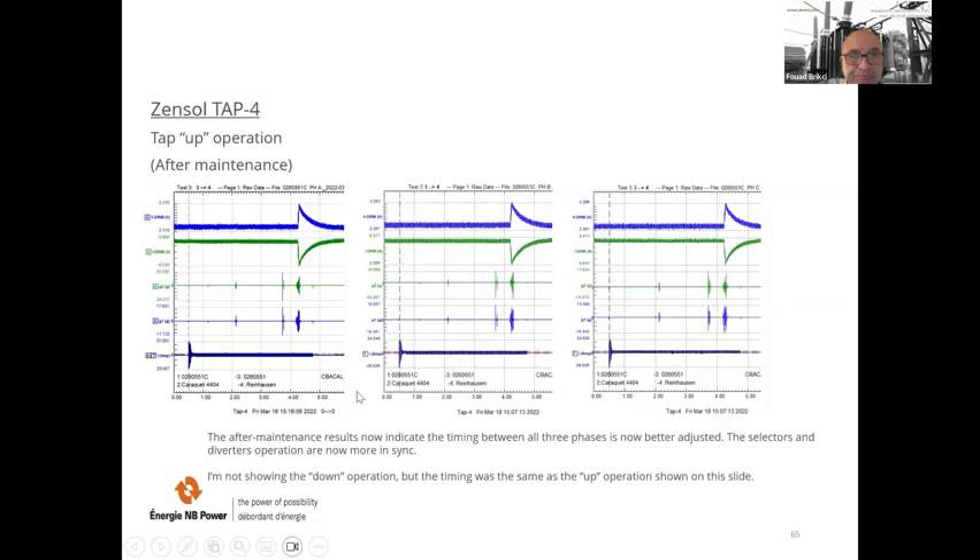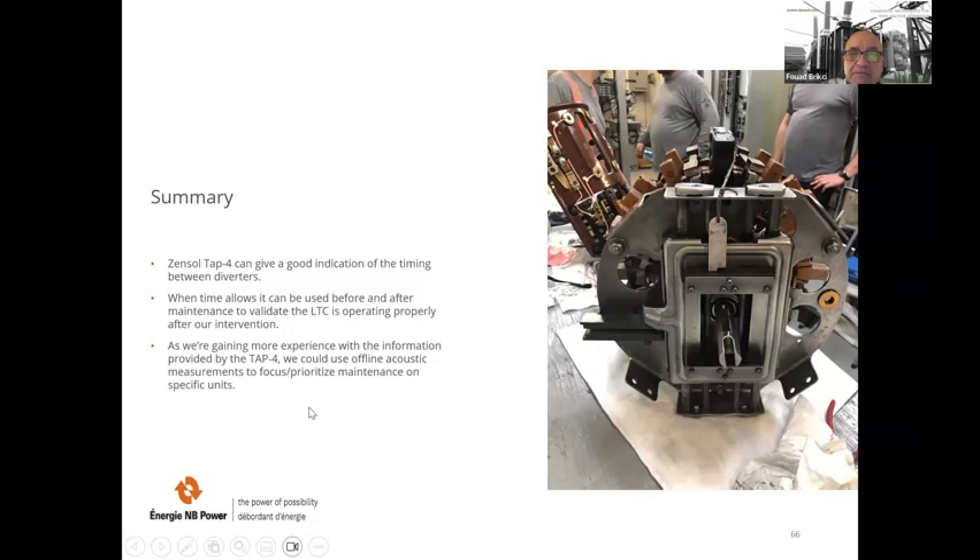In summary, the Zensol TAP-4 can give a good indication of the timing between diverters. When time allows, it can be used before and after maintenance to validate the LTC is operating properly after intervention. As more experience is gained with the TAP-4, offline acoustic measurements could be used to focus and prioritize maintenance on specific units — exactly the kind of benefits described at the beginning of the presentation.